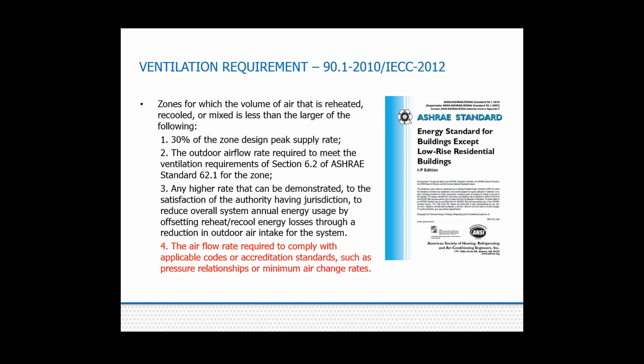So one thing I wanted to point out is that sometimes it's not just that you may reduce the flow, it's that you must reduce the flow. If you're in an area where IECC 2012 or newer, or ASHRAE 90.1 2010 or newer is your energy code, it is actually required that you do that because if you're reheating the air, which is normally the case in healthcare, there are really only 4 exceptions left that allow you to reheat air, and the only one that applies to most healthcare spaces is exception number 4, which is the airflow rate required to comply with applicable codes or accreditation standards, such as pressure relationships or minimum air changes. And I'll do a couple examples of that. Next slide, please.